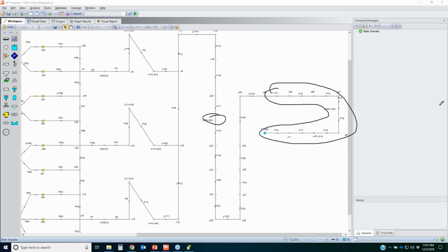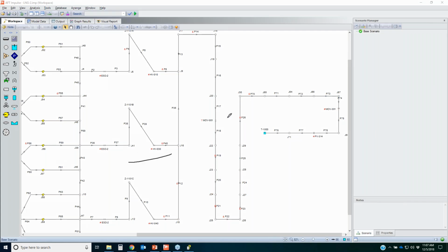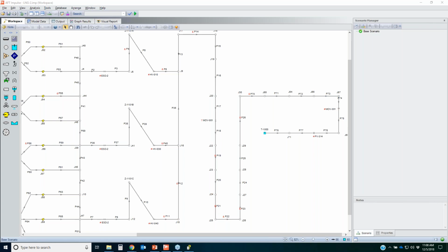What's going on is you have some elevation changes in those areas, and when your elevation goes up to some high points, your pressure is going to decrease. So when your valve starts closing and this starts to shift downwards, this pressure, which is located right here, drops to vapor pressure. So you don't want to look at only the outlet of pipe 73.